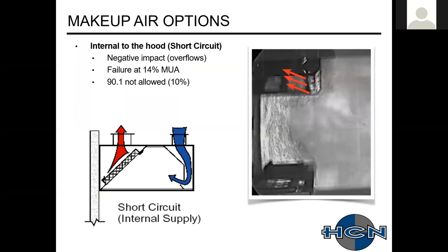The next thing up for their testing was internal compensating hoods, or short circuit. They were developed as a strategy to reduce the amount of conditioned air required by the exhaust system by introducing that portion of that air into the hood cavity itself.